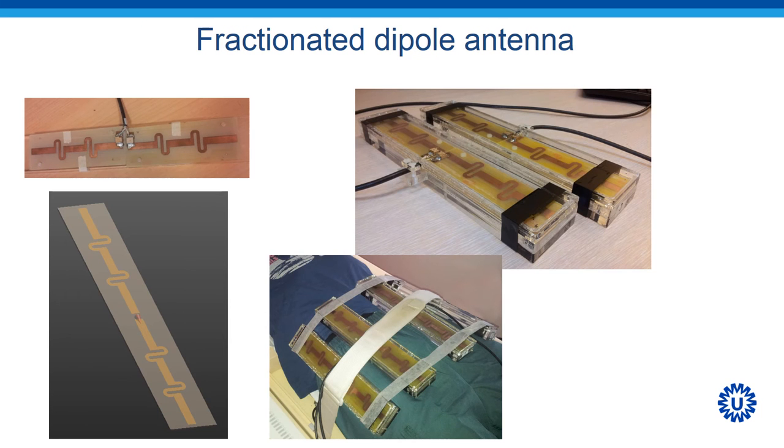From these findings, we have developed the fractionated dipole antenna, which is an antenna where the legs are divided into segments, and the segments are interconnected with a meander that serves as an inductor. We have created an array of eight elements for pelvic imaging, where the elements are aligned around the pelvis, as indicated in the image.